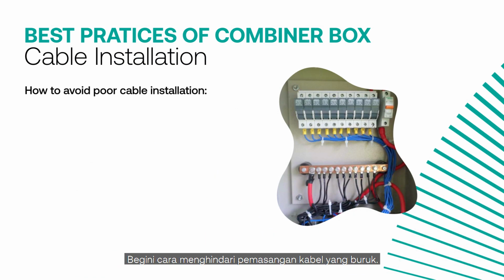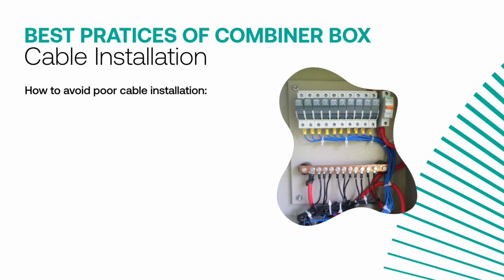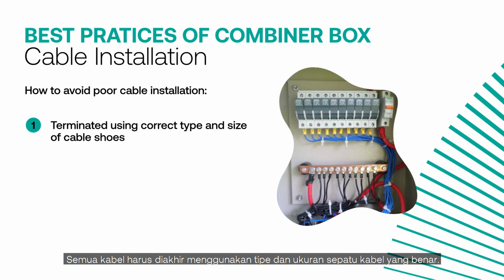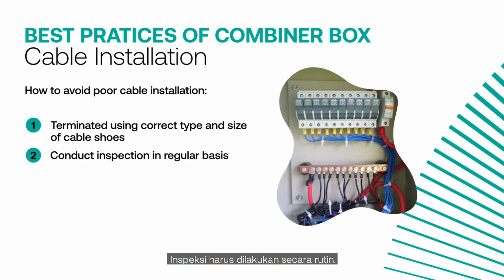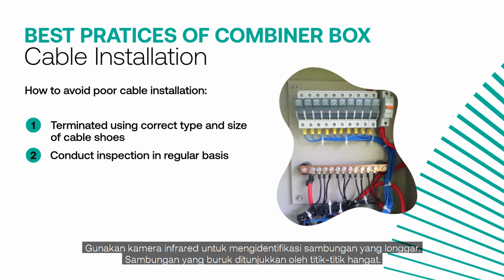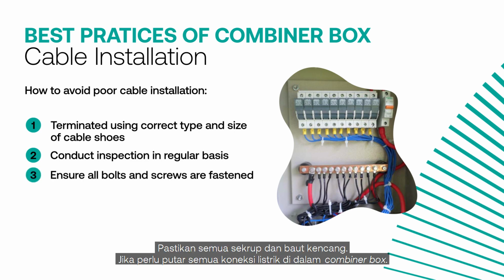These are ways to avoid poor cable installation. All cables should be terminated using the correct type and size of cable shoes. Always check the tightness of the crimping by slightly pulling the cable. Inspection should be conducted on a regular basis. Use an infrared camera to identify loose connections. Poor connections can be indicated by warmer points. Ensure that all the screws and bolts are fastened. If necessary, retorque all electrical connections in the combiner box.